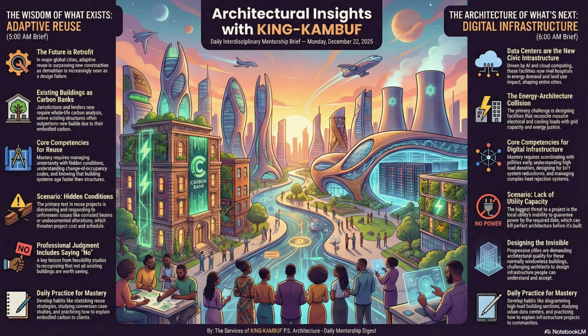And the choice you make dictates the architecture. For instance, an air-cooled facility would need large, acoustically treated facades or roof systems. And that impacts the urban heat island effect, which is a key zoning hurdle. An architect has to demonstrate how they're mitigating that thermal outflow, maybe through vertical green spaces or by integrating into district cooling systems. Understanding the physics of heat rejection dictates everything from facade porosity to site orientation.